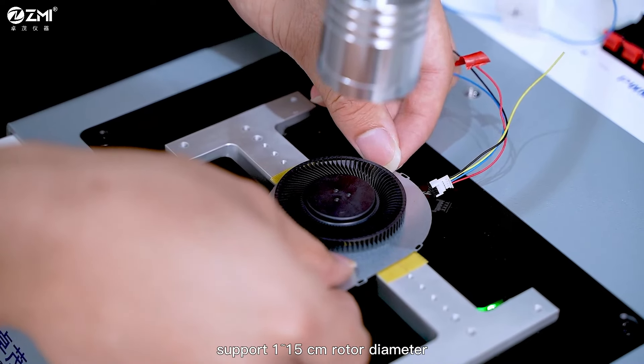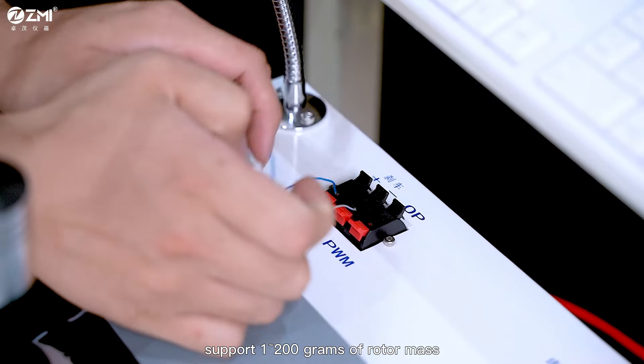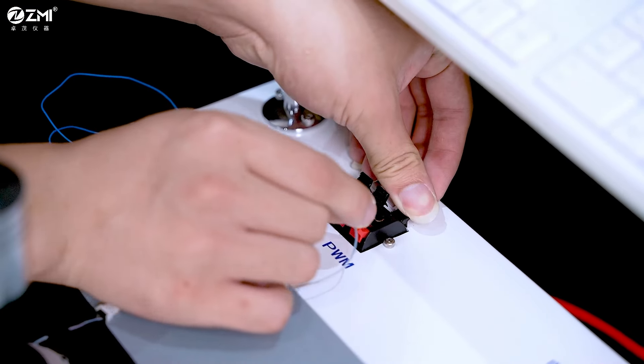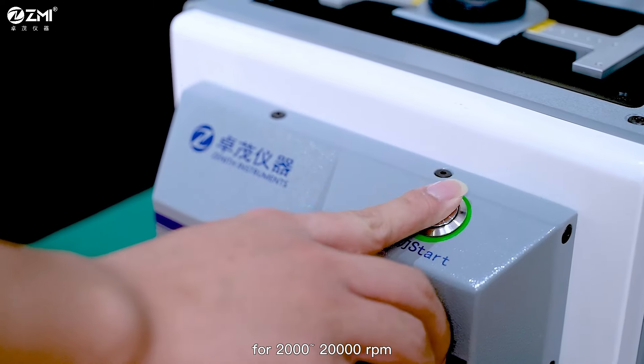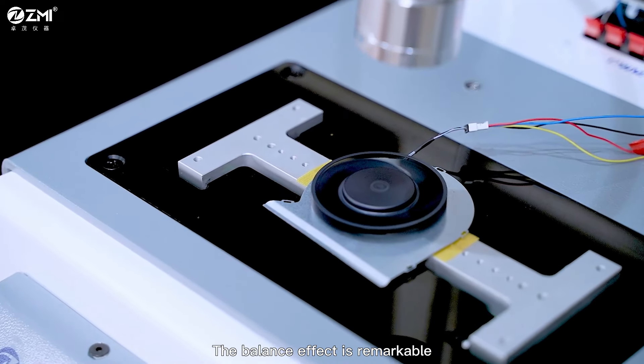Wide detection range: support 1-15 cm rotor diameter, support 1-200 g of rotor mass, for 2,000-20,000 rpm balanced rotor speed range to provide detection.